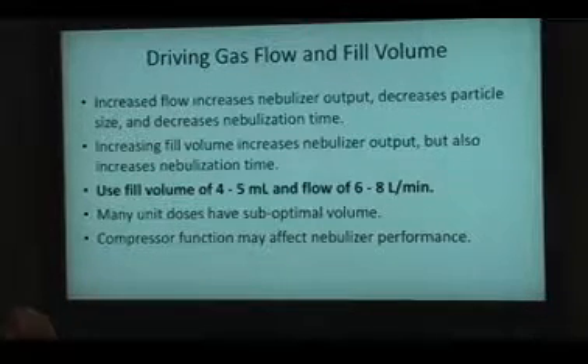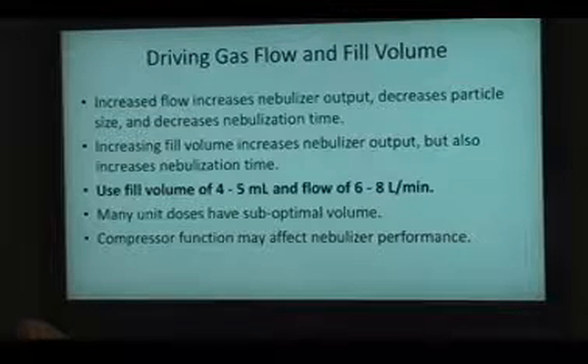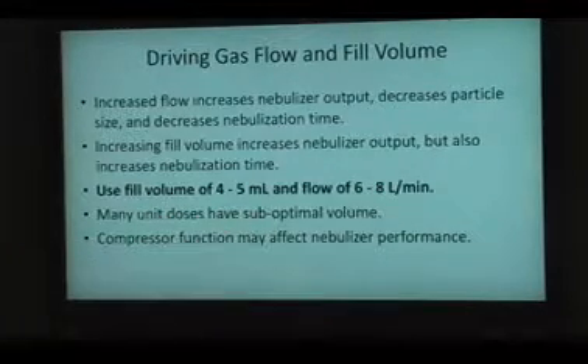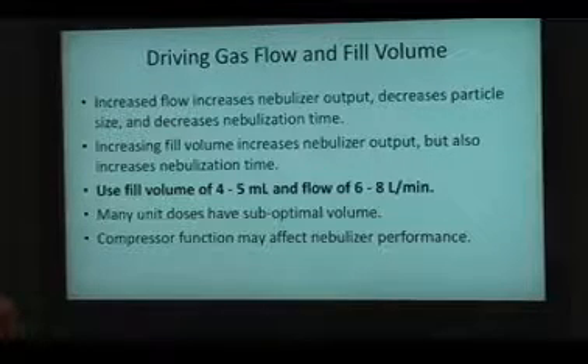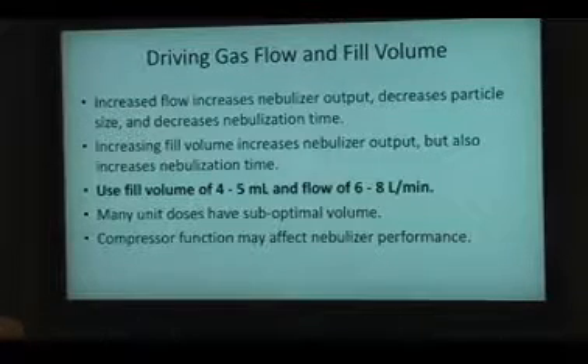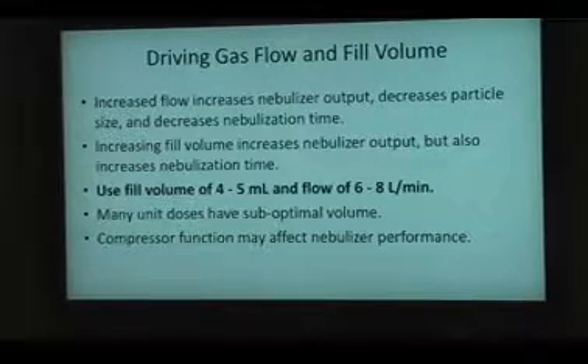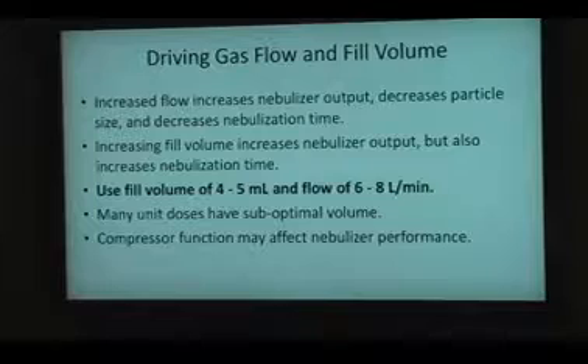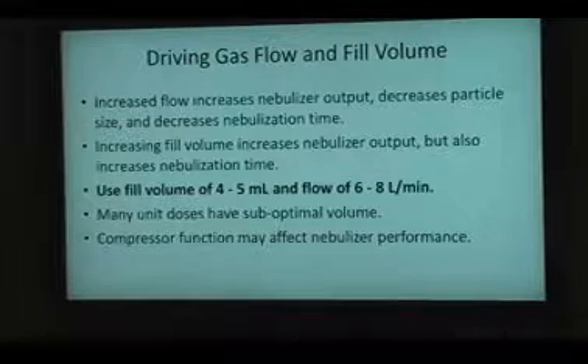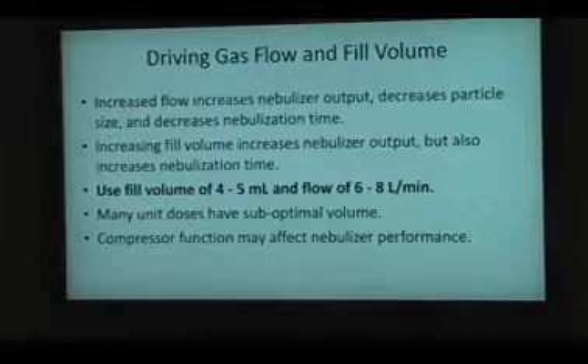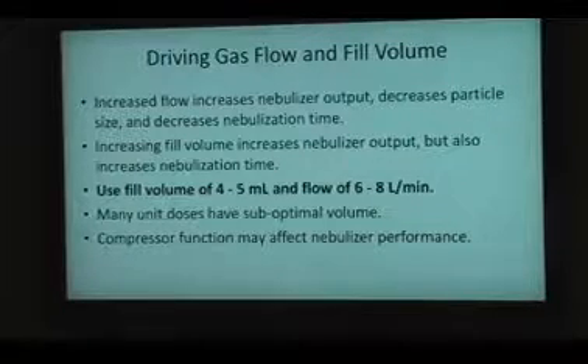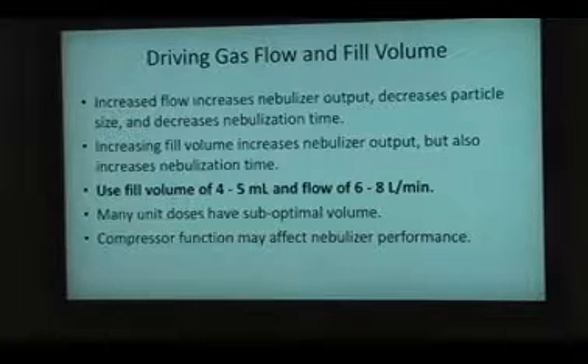And there's a lot of it that's lost in the dead volume of the nebulizer. Right. So that's why the fill volume of 4 to 5 mLs is important. Most jet nebulizers have a dead volume of about 1 milliliter. So it's about a milliliter of the drug that never gets aerosolized. So if you only put 2 milliliters of drug into the nebulizer, half of it is wasted. If you put in a 3 ml vial of albuterol, a third of it is wasted. And for bronchodilators, it might not matter that much. They're dirt cheap, so you could just put in a second vial if you don't get the effect with the first one.